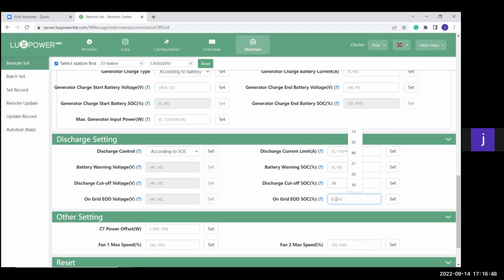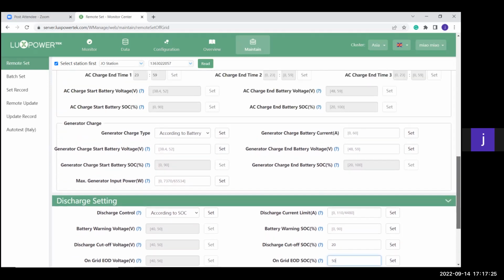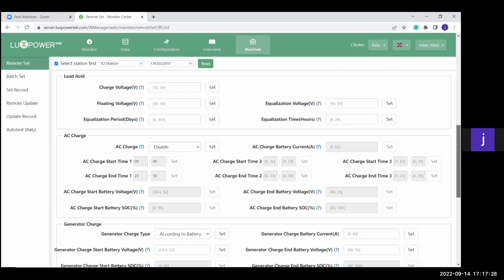Now, your on-grid EOD is the value at which your inverter will kick back to Eskom while Eskom is available. So if I set it to 50%, my batteries will be drained to 50%, and then it goes back to Eskom while the grid is available. And once the grid fails, it will go to the discharge cutoff SOC. That's the lowest that the batteries will be drained while the grid is not available. So this gives you the capability of using a small amount of your batteries every night and still leaving a small amount for when there are unforeseen power outages in certain areas. So that's how you're going to do a solar, battery, utility system.